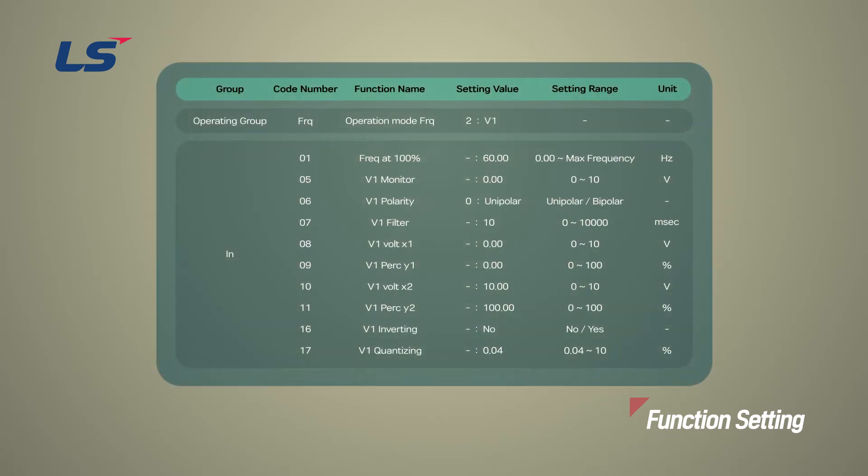Parameters related to analog input can be set in ingroup. First, set ingroup 6 to unipolar, because we will not use negative voltage here. If the range of minus 10 volts to plus 10 volts is needed, set it as bipolar.